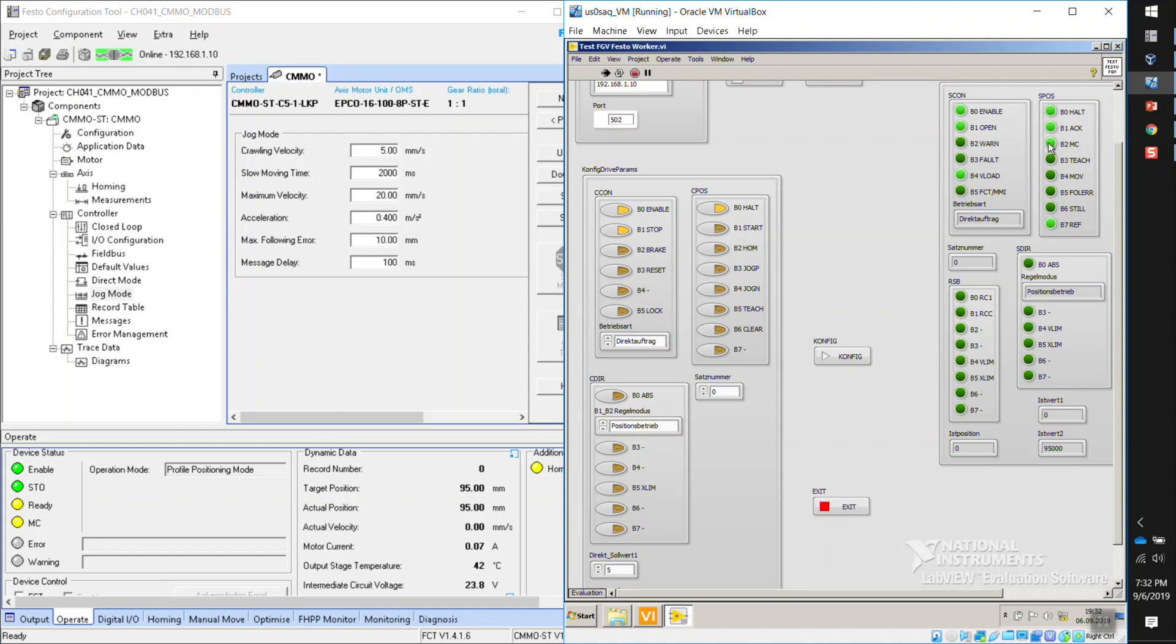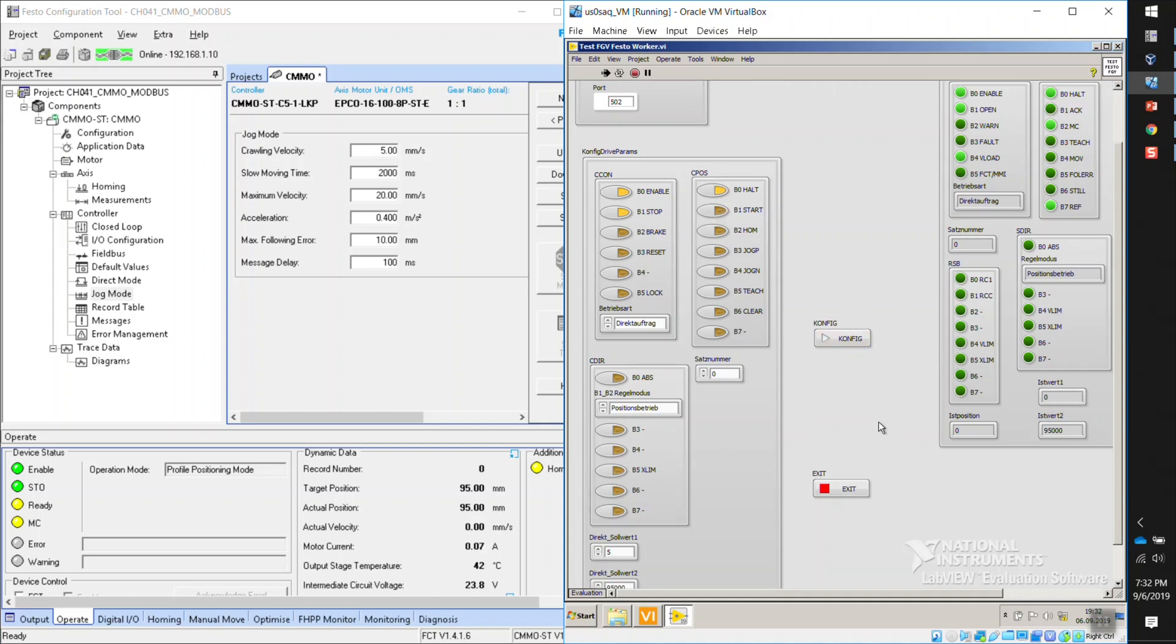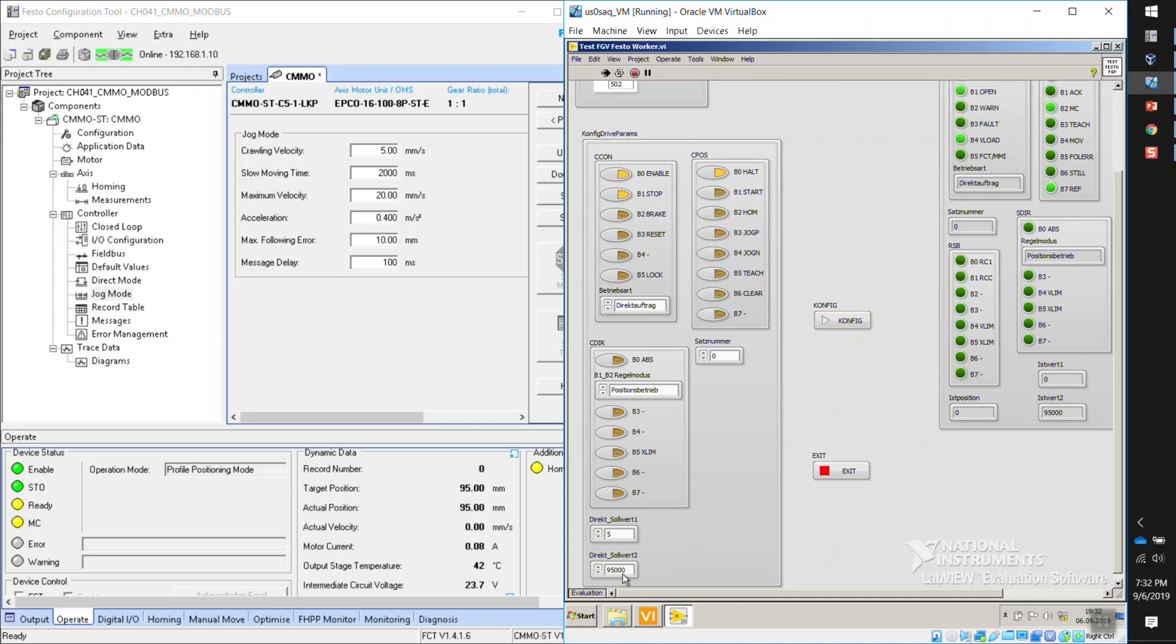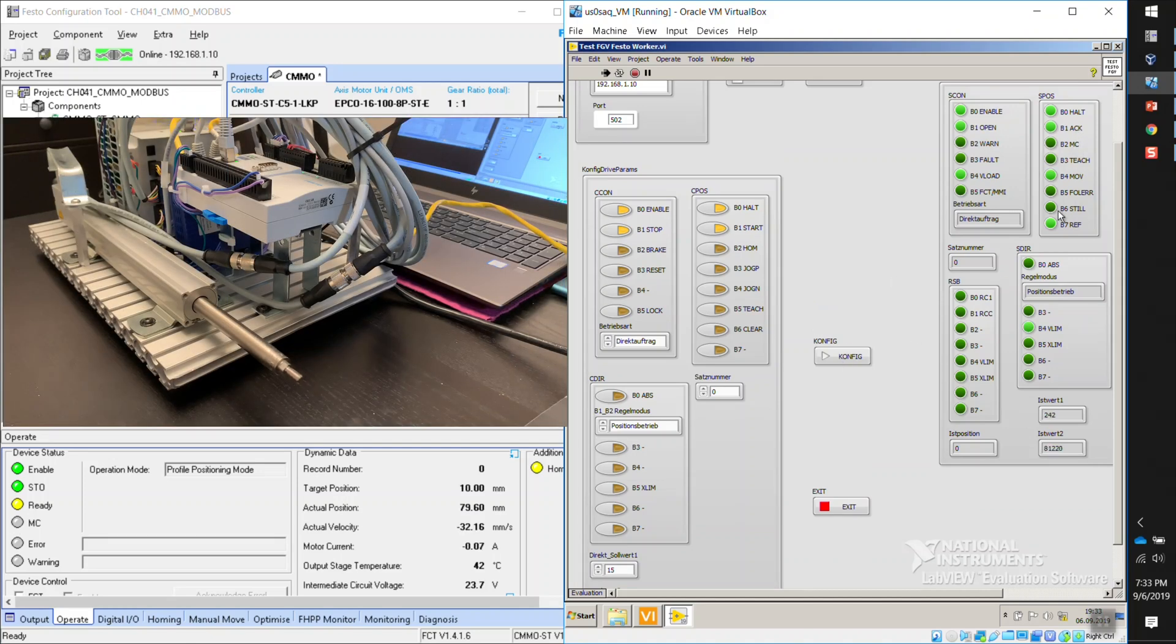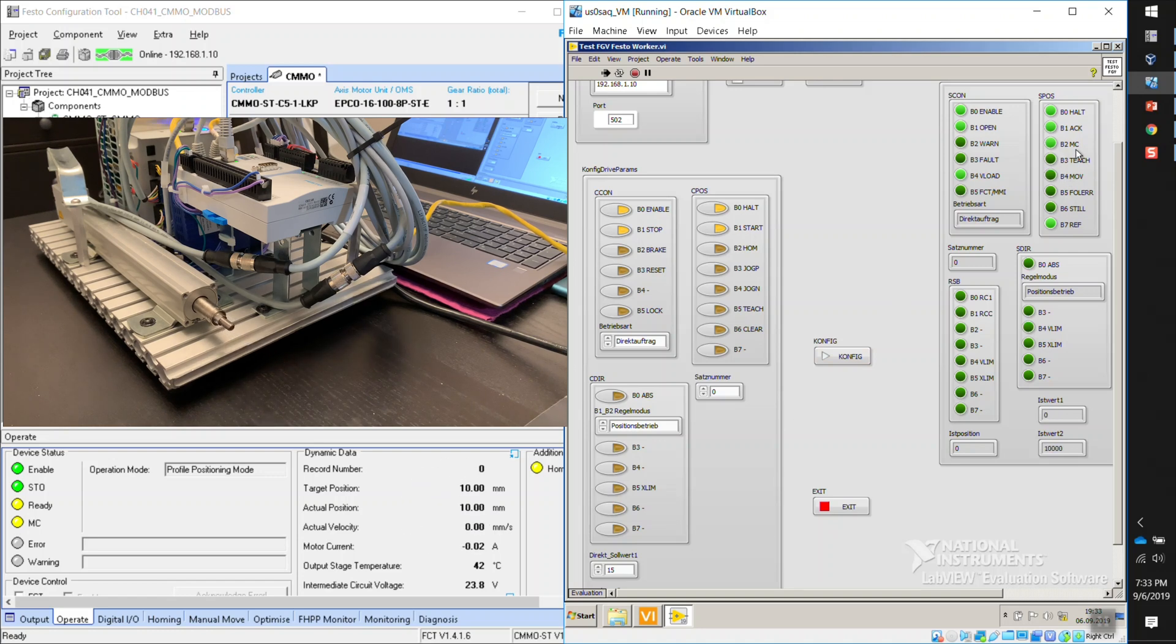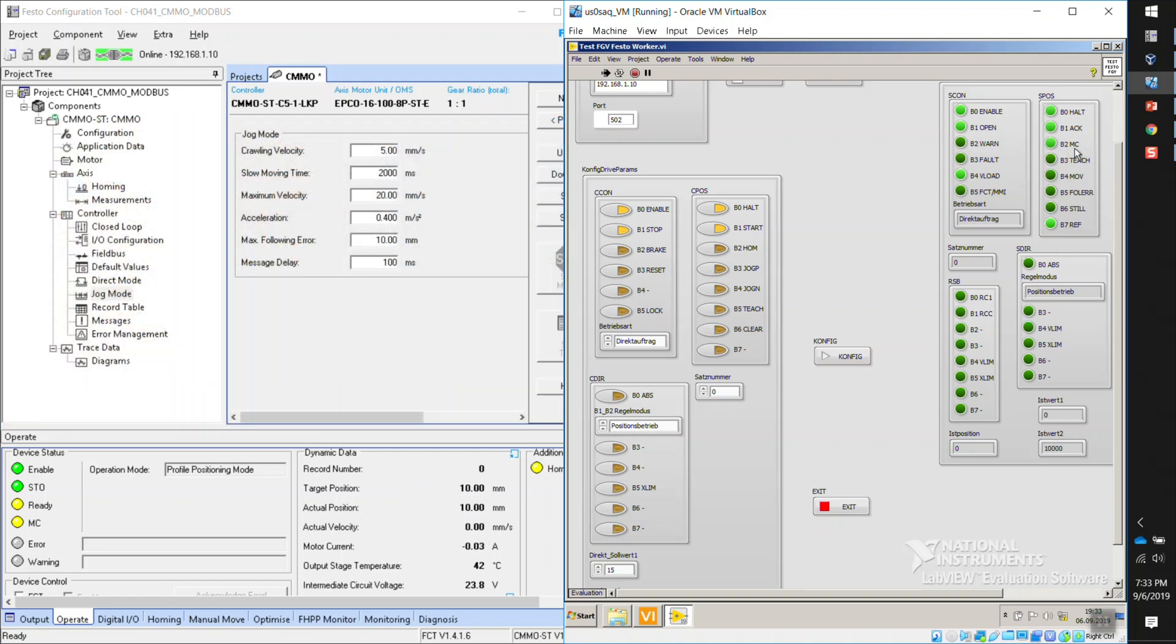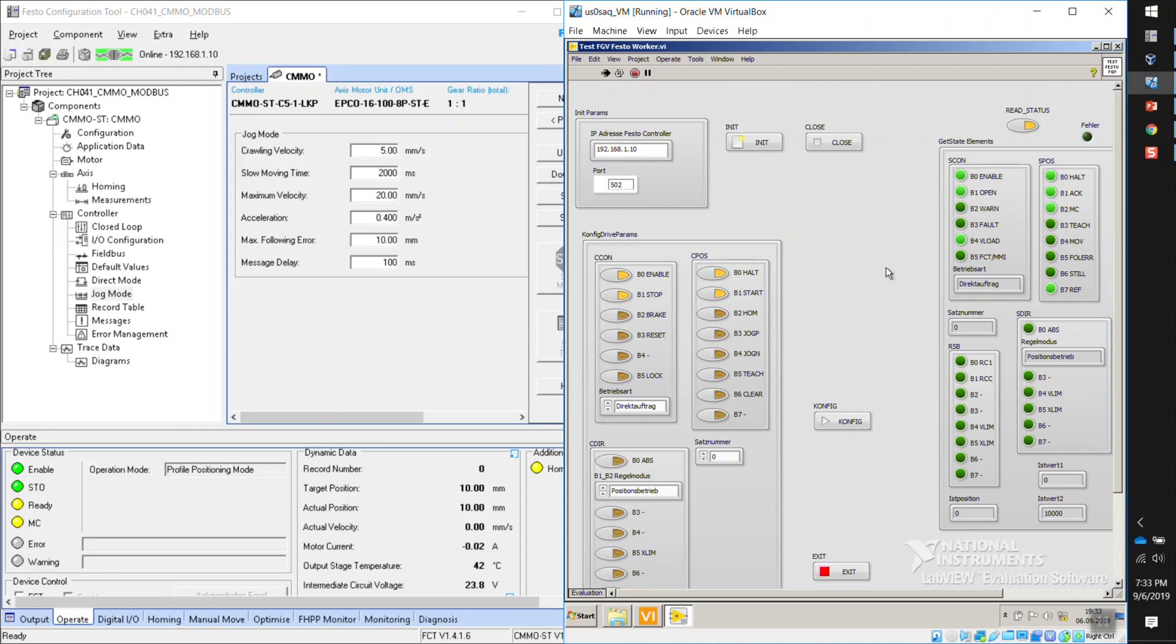So anyways, this acknowledge should go away now that I deactivated the start. Let's send it back to, I don't know, 10,000, for example, which is 10 millimeters, at a different speed, let's say 15. So start, and we should see the acknowledge and the motion complete should go away, I believe. So motion complete goes away. When we reach 10, we get the motion complete.